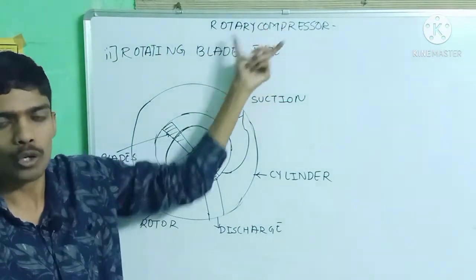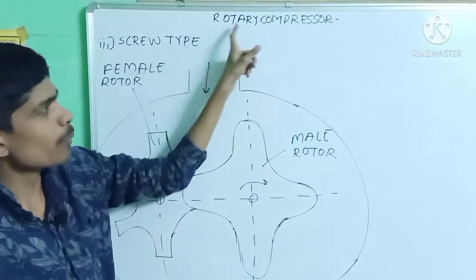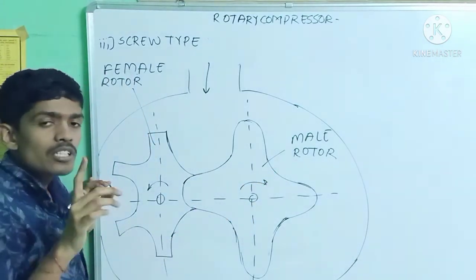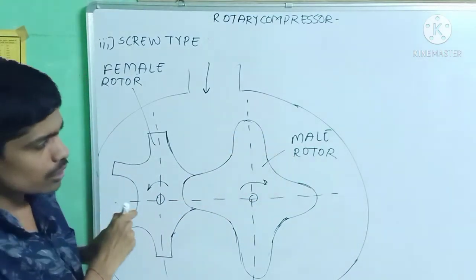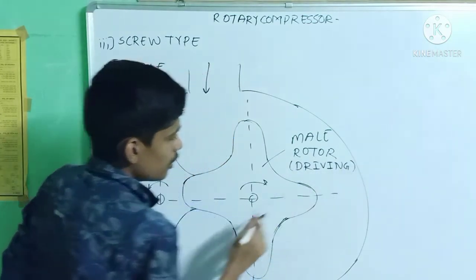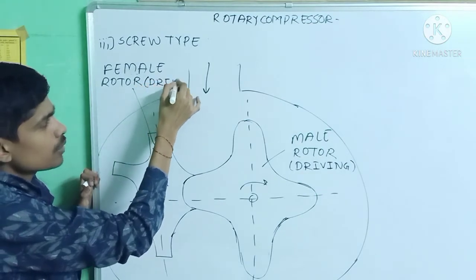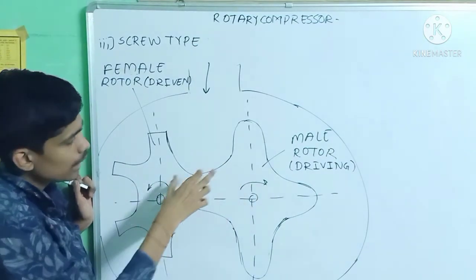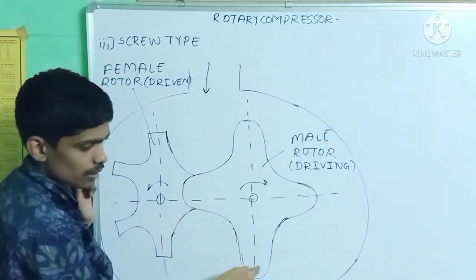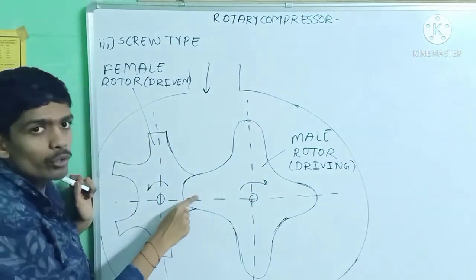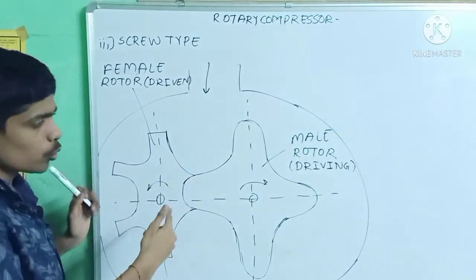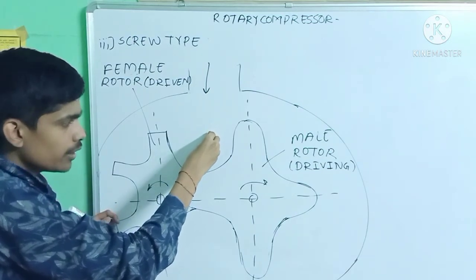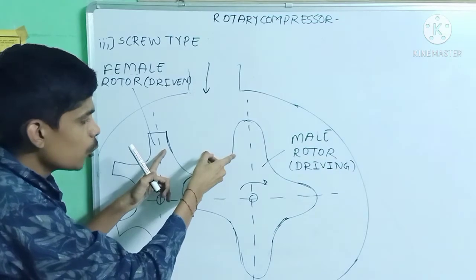The third and last type is the screw type rotary compressor. It consists of a female rotor and a male rotor. The male rotor is connected to the motor and is the driving rotor; the female rotor is the driven rotor. They rotate in opposite directions and are engaged together. The male rotor has four lobes and the female rotor has six helical flutes. When the rotors rotate, low pressure, low temperature vapor refrigerant enters and passes through the space between the male lobes and female flutes.